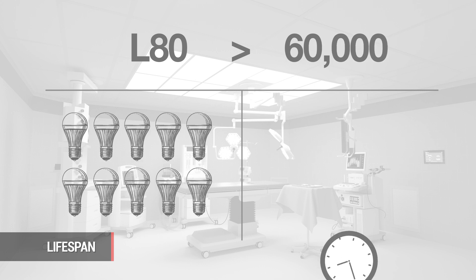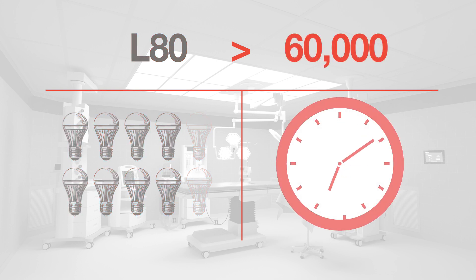The lifespan of an LED is measured as a function of brightness over time. L80 greater than 60,000 means that the lights will maintain at least 80 percent of their brightness for over 60,000 hours.